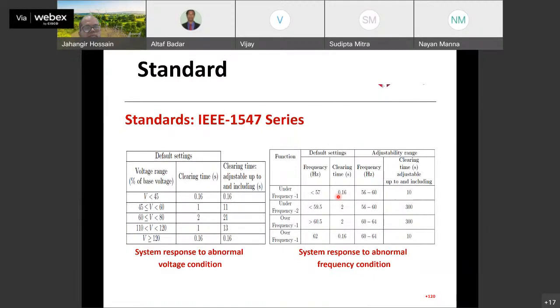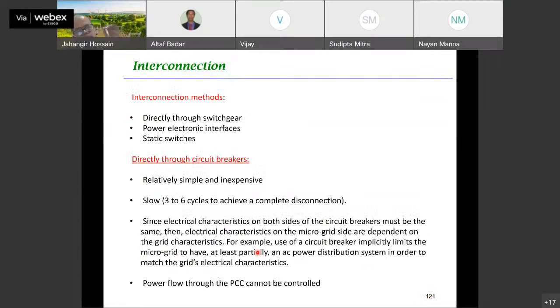Now that's some of the applications, but for microgrid design there is the IEEE standard 1547 series you can follow, so that for different ratings, if something happens abnormally, you know the time within which you need to clear it - not only for voltage but also for frequency level. It also has some standards for communication purposes as well.